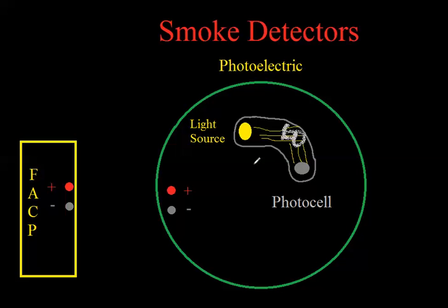The circuitry inside the photoelectric smoke detector interprets that current and puts the device into alarm. If we were to wire this to our fire alarm panel, it would be powered up the same way these have been all along. This is just a two-wire smoke detector, I should point out. There are also four-wire smoke detectors, which the wiring's a little bit different, and I'll explain that in the future.